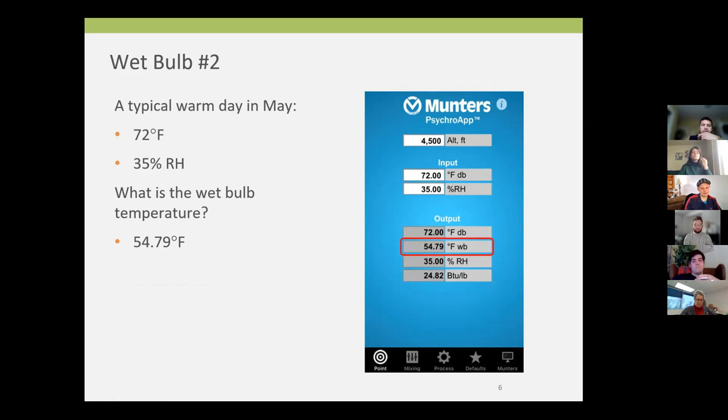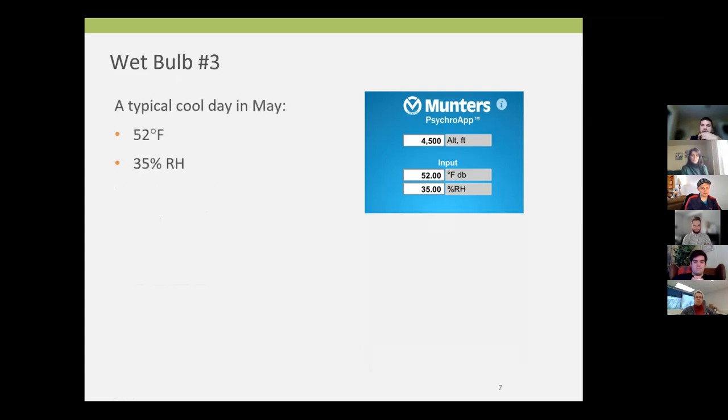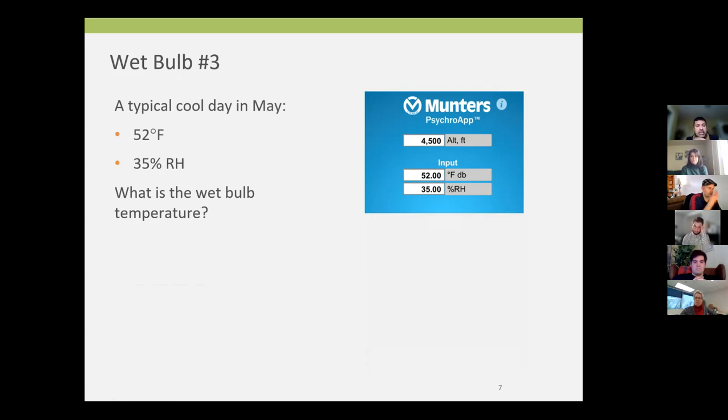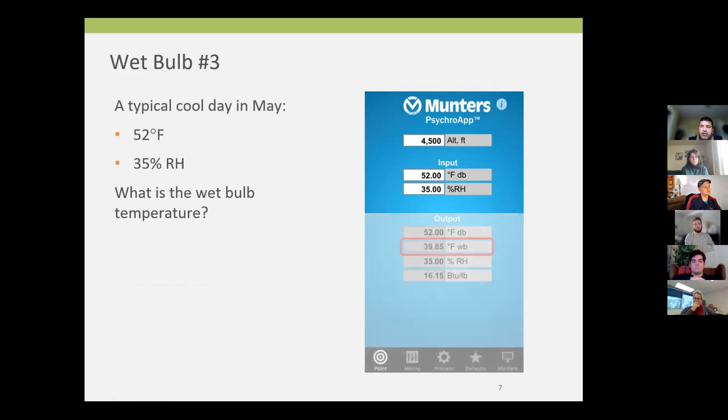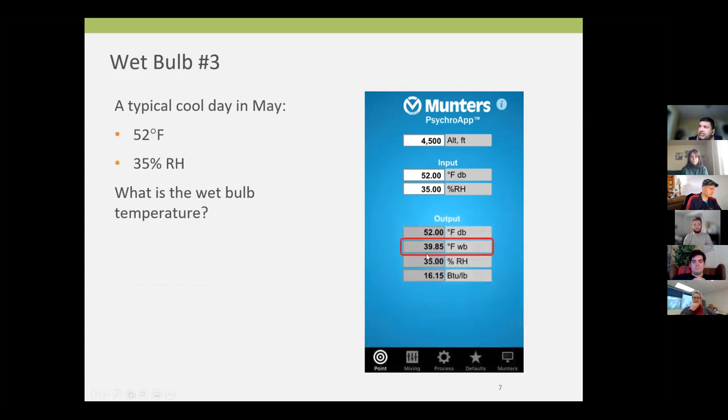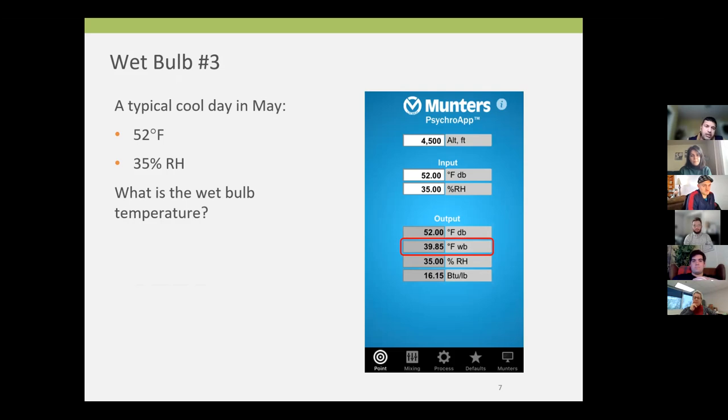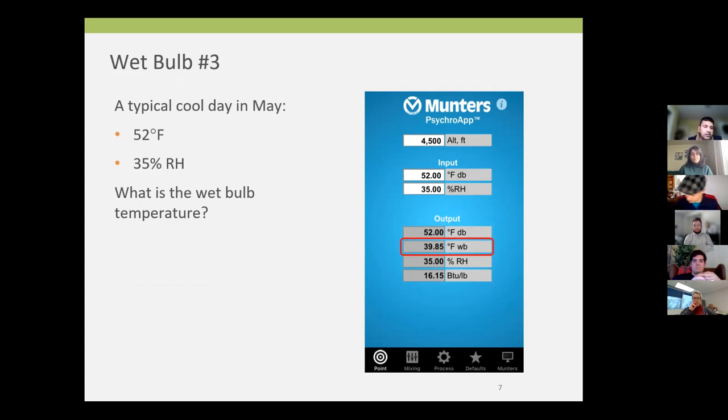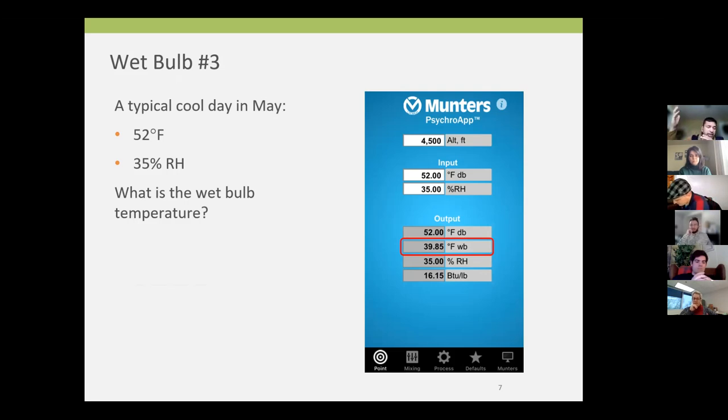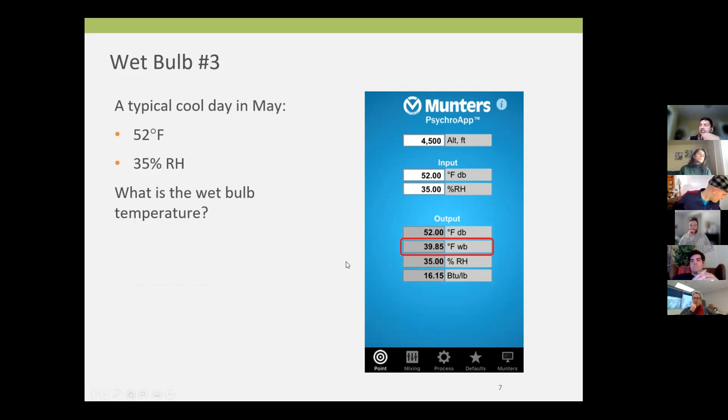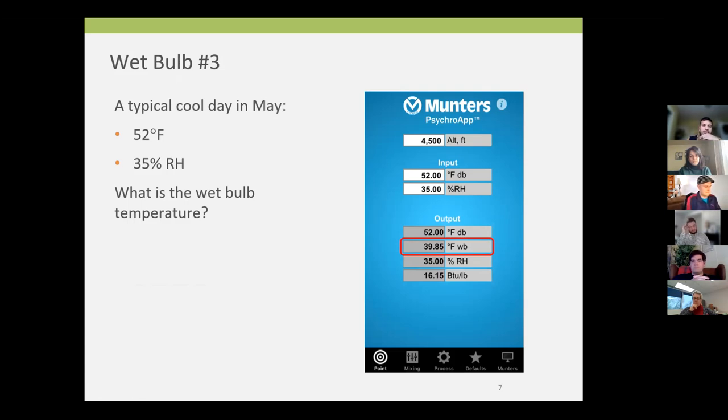Sonny, have you ever tested this with a sling? I have not, but I have tested this app against actual measurements in a cooling tower, and it's been pretty spot on. I do this test all the time. I basically pop open the app, see what the sump temperature should be theoretical, and if I'm within a few degrees, I know I've got it there. So I check the efficiency of a cooling tower using this app all the time. The dry bulb temperature is 72, relative humidity 35, pretty typical Utah day. The wet bulb temperature is 54 as the output. 54 feels pretty cold. This is not a fun day on the lake. This is why you don't jump into lakes in April and May. Just to illustrate how wet bulb changes. First example was 100 degrees, 25%. Second example, 72, 35%. And the third example, 52 and 35%. You'll see you can get 39 degrees theoretical. That's how cold you can get that water.